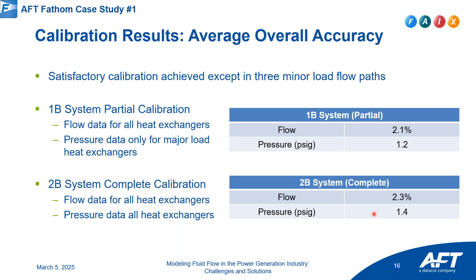Using the automated goal seeking, we were able to match their flow measurements within 2.1% and all the pressure measurements on average on the 1B system within 1.2 psi. And on the 2B system, the flow is matched within 2.3% on average and 1.4 psi. So that was the end result on that particular project. In the end, they had two models, the 1B and the 2B system, that had been calibrated for their in-operation piping, so they could use that for design decisions going forward with, for example, changing pipe routing.